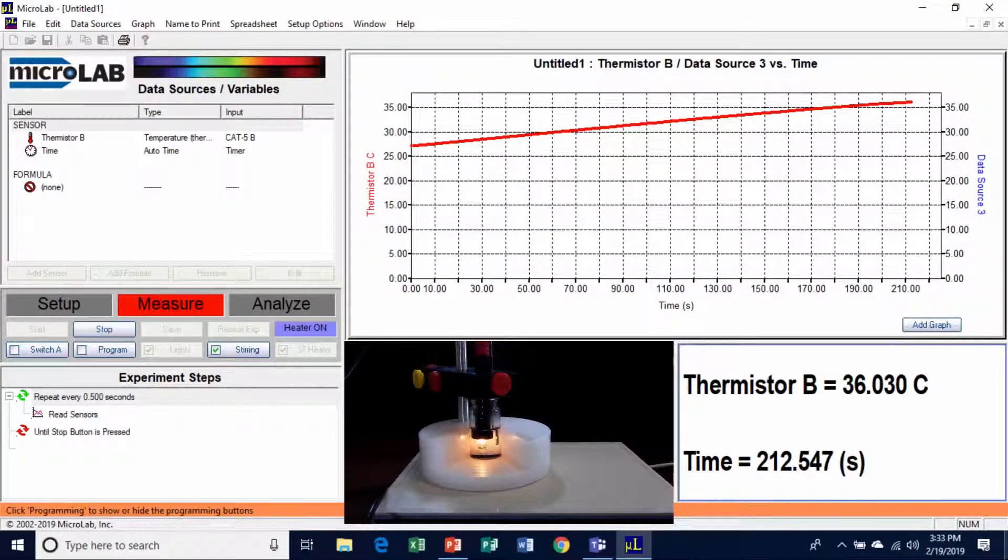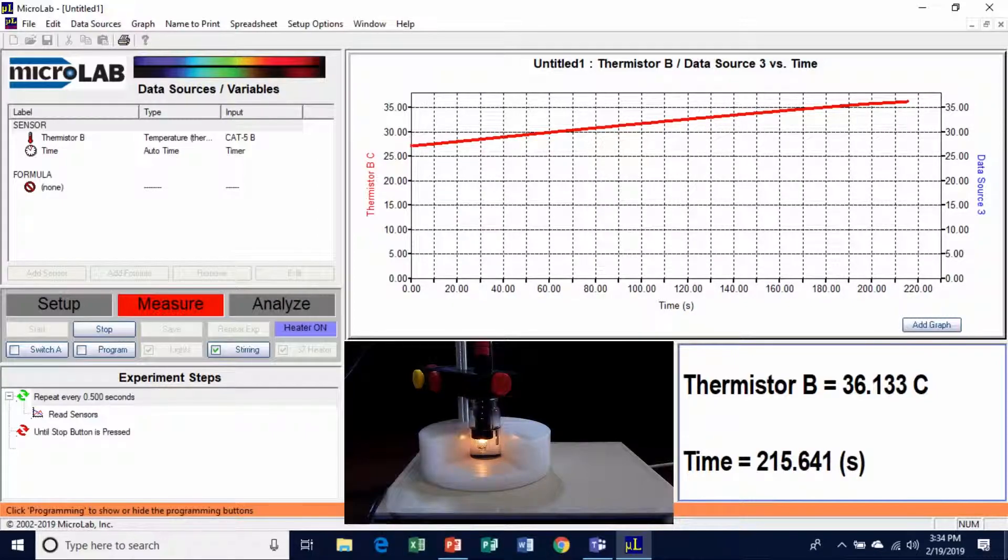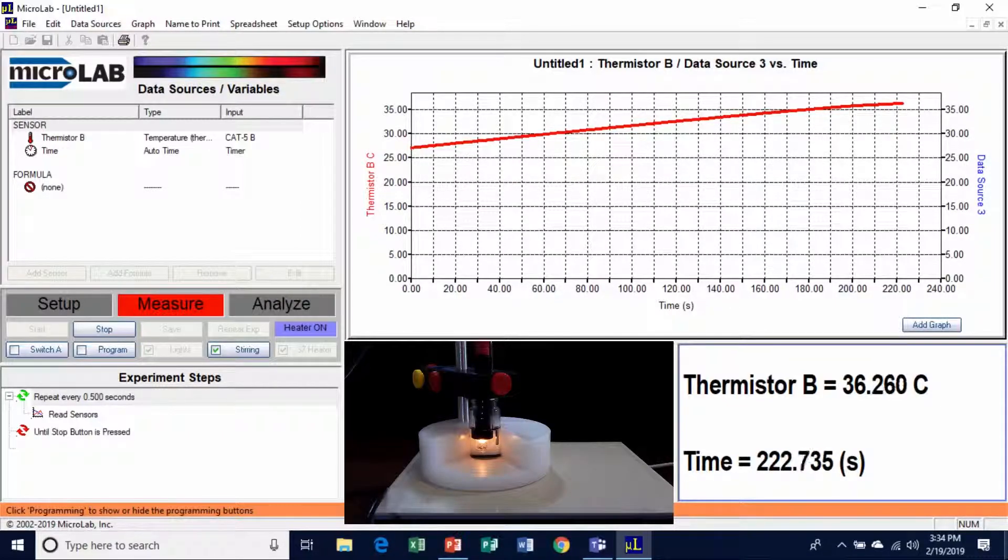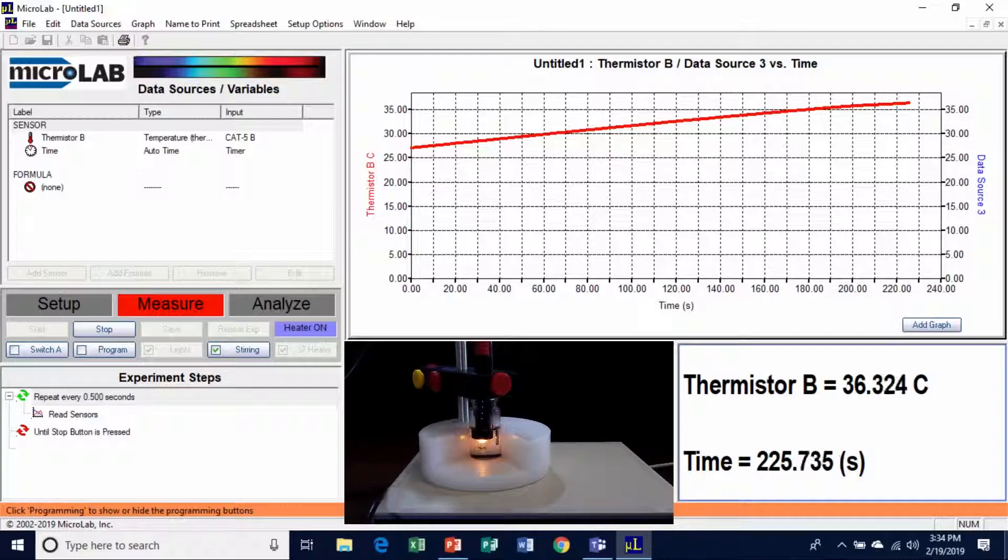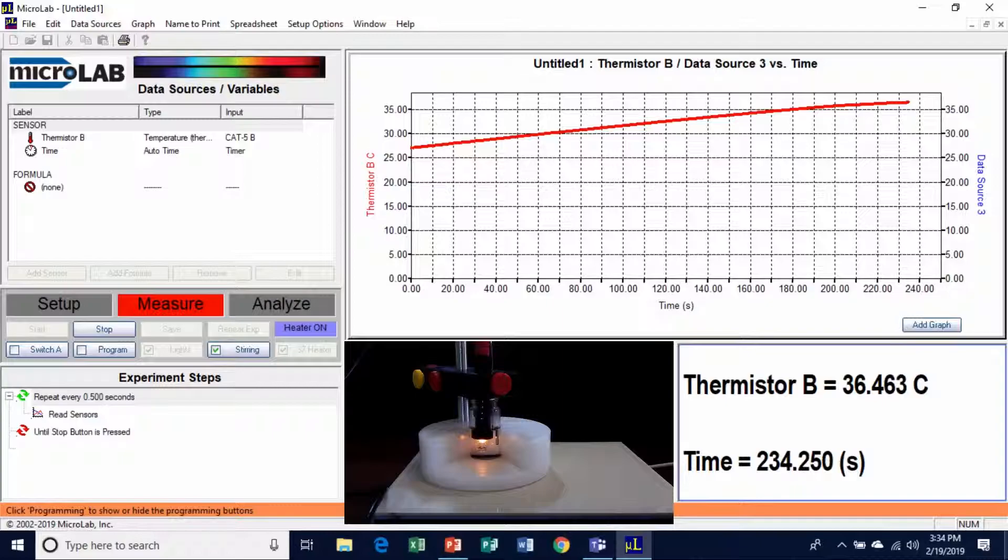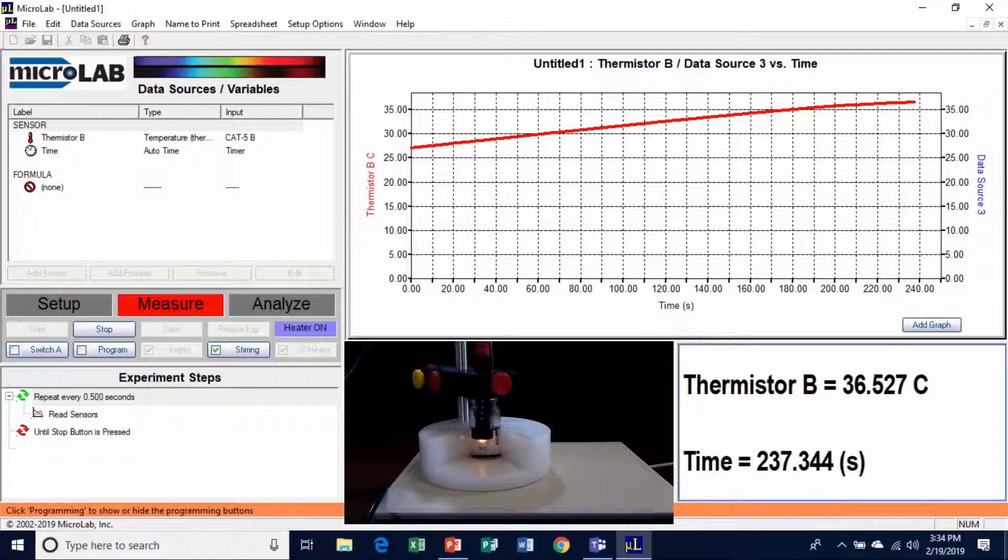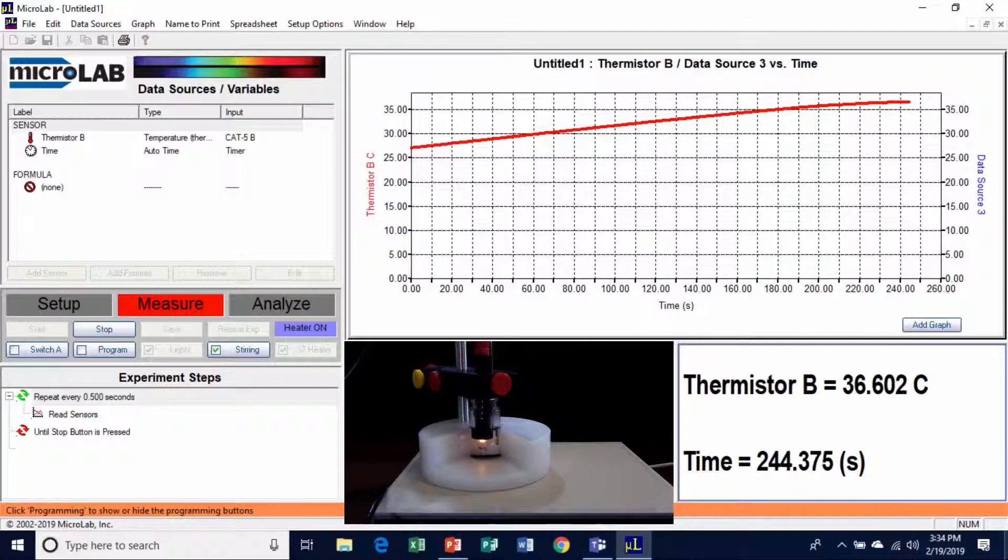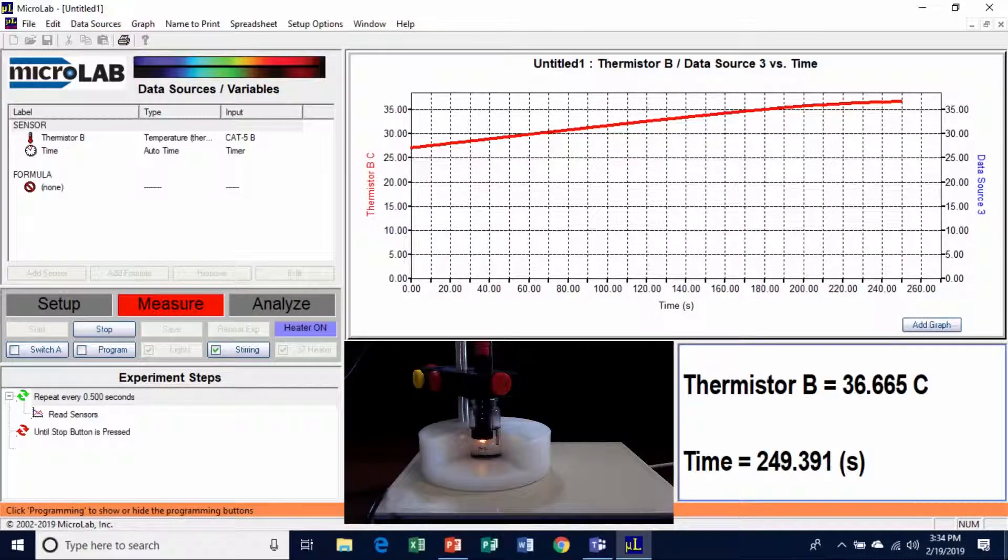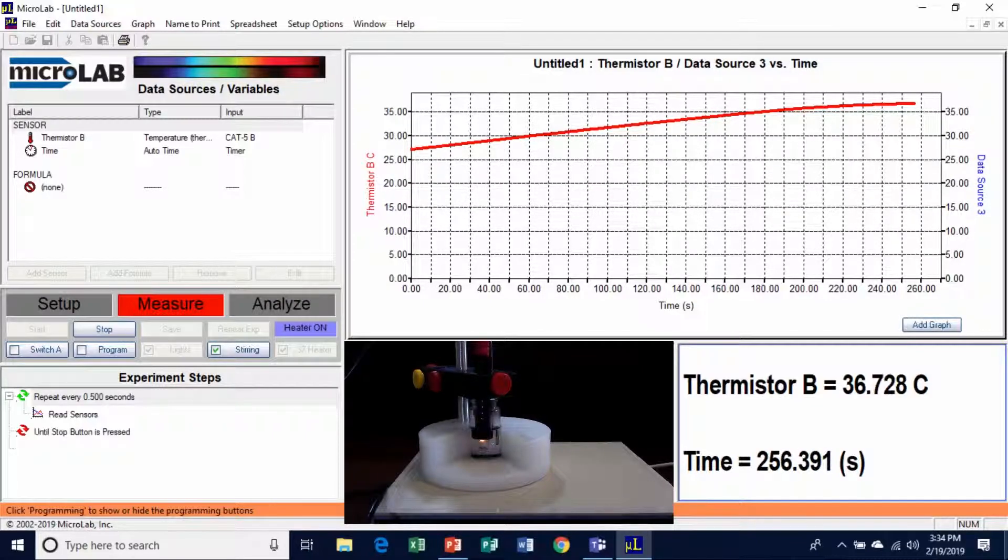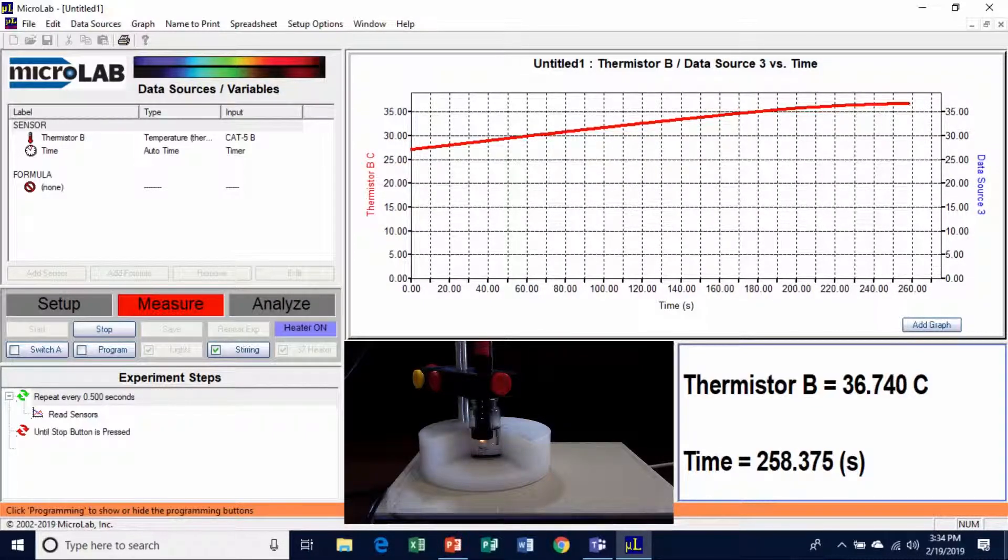Okay, this is approaching 37 degrees. And did you notice that the lamp just dimmed? There it dimmed again. As we approach the target temperature, the proportional control reduces the power to the heater. So we ought to just coast right up to 37 degrees. We have about 4 tenths of a degree to go. It's getting closer. And do you notice how straight a line that is? The heat input was very constant right up until just a few seconds ago, when all of a sudden you can see the heat going down and the graph flattening out. And it's coasting up to approach 37 degrees there, it dimmed again. When it gets there, we're going to let it run a little while. And then we're going to stop it and we're going to measure how flat that line is, how stable the temperature is.